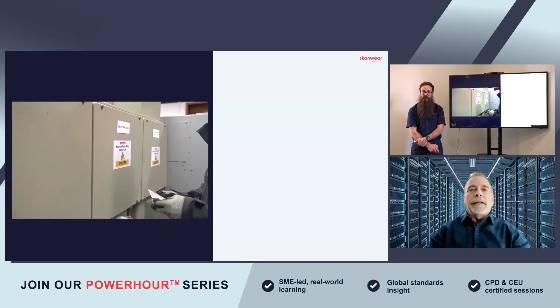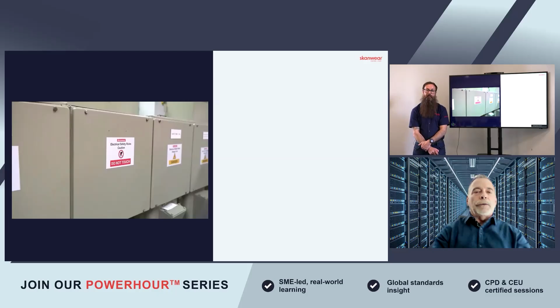So, back to the live dead live performance. It's important to reiterate here that all of those involved with the work must witness that live dead live, and it has to be done at each work location as per the new NFPA 70E 2024 standards. But at this point, once you've proven everything de-energized, with zero energy verification, and you go to the back of your panels with medium voltage, we would install grounding clusters. But prior to doing that, medium voltage can have a capacitive charge that you have to dissipate through grounding sticks or whatever. It's important to take out that capacitive charge and then install your grounding clusters.